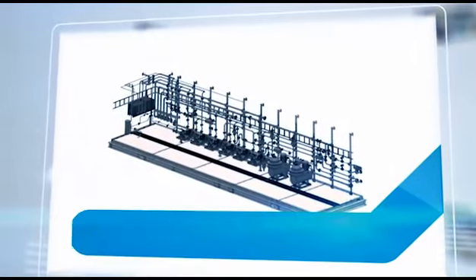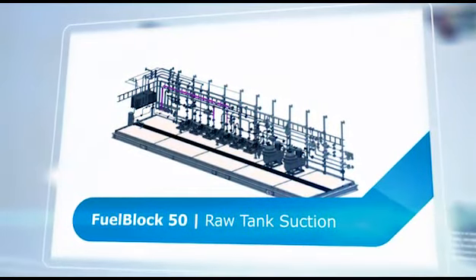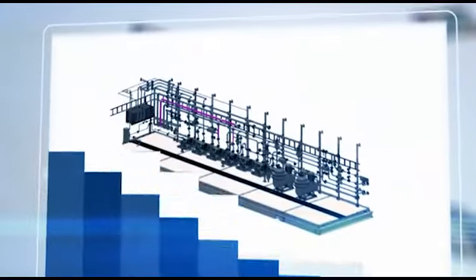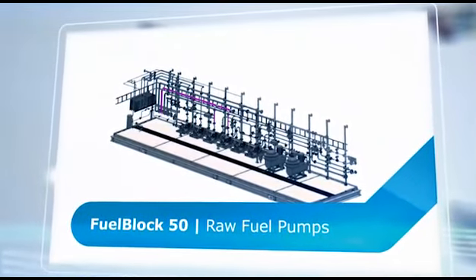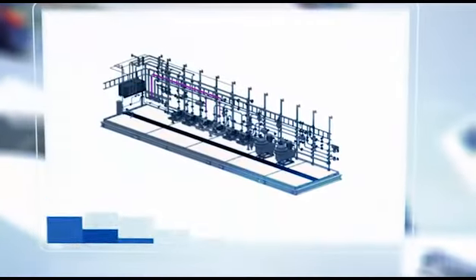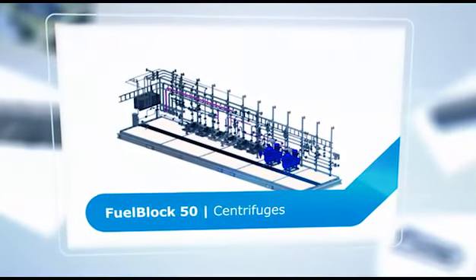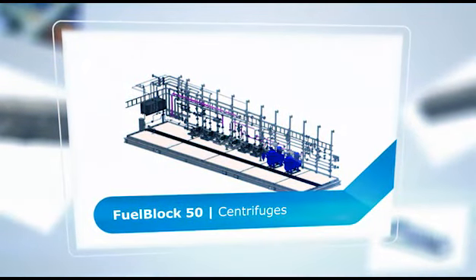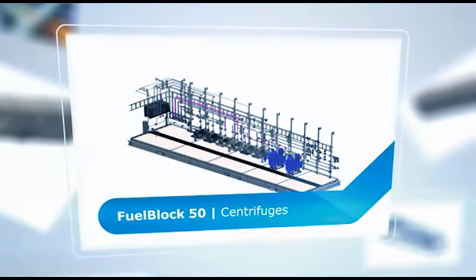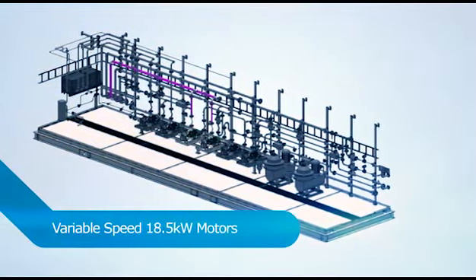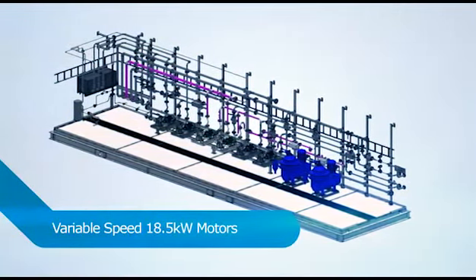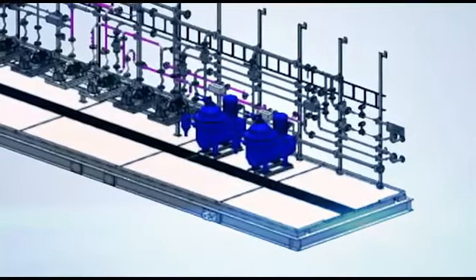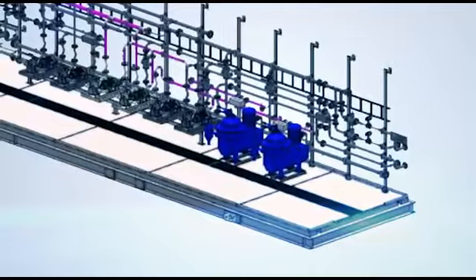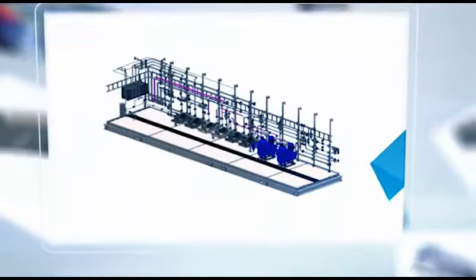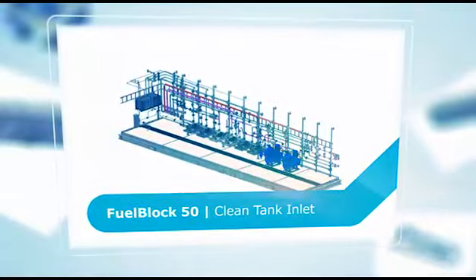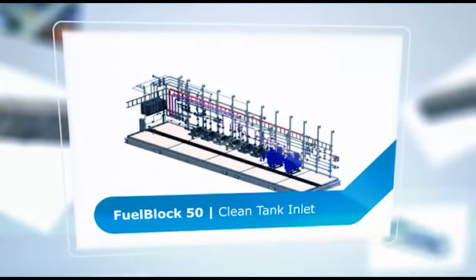The raw tank suction header is connected to the raw fuel tank via a floating suction arrangement. The raw fuel pumps draw fuel from the tank to their dedicated centrifuge for treatment. The centrifuges are rotating disc-type separators. They process continuously to produce clean fuel and heavy phase discharges. Variable speed controlled 18.5 kilowatt motors drive the bowls via a centrifugal clutch. Bowl operations and discharges are performed using process water. Treated fuel from the centrifuge is transferred to the clean fuel storage tanks via the clean tank inlet header.